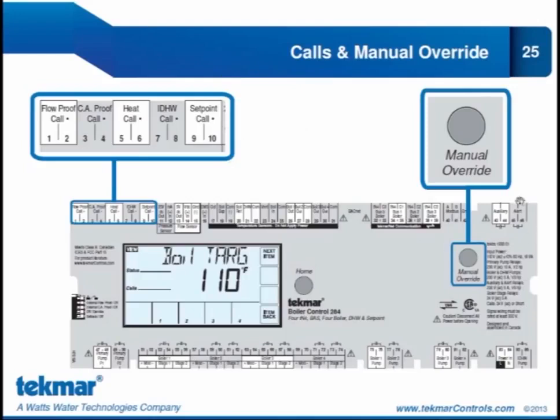This is the manual override button, which is a new feature for the 284, and it replaces the max heat function. The problem with the max heat function is that not only did it operate the equipment, but it turned the boilers on too. And sometimes you may want to try and operate the equipment without turning the boilers on. And the manual override function allows you to do that. There are 5 different modes that you can select. And if you select the hand mode, you can actually choose the equipment that you want to operate one by one. So it allows you that flexibility to test your system, see how it's operating the way you need to test it, as opposed to the max heat function.